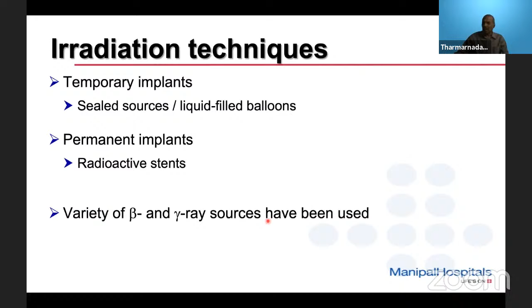The dosimetric requirement of these sources for a temporary intravascular implant is to deliver a dose of 15 to 20 gray. So whatever source we are using, we shall be able to deliver a dose of 15 to 20 gray to a 2 to 5 centimeter length. Rarely it can go up to 6 centimeters. So normally 2 to 5 centimeter length of arterial wall at a radial distance of about 2 millimeter from the source center. The source shall be able to minimize the dose to tissues outside the region of angioplasty. To take as little time as possible, the source shall be of that activity and that design such that the treatment time is as little as possible.